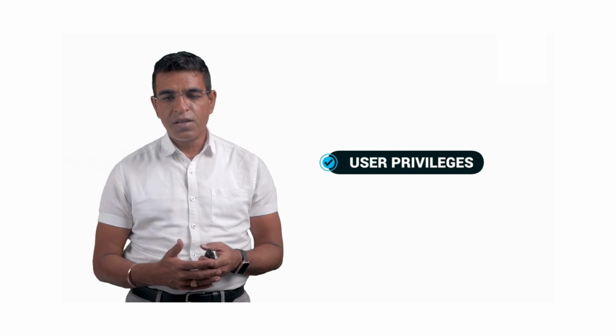Coming to passwords, many times we see common passwords being used. Where people share passwords, it is not possible to identify who creates or changes a record. So it has to be very clear that we should never use common passwords. Everybody should have their own individually identifiable password, known only to them. Coming to user privileges: the system configuration of the software does not adequately define or segregate user levels, and users have access to inappropriate software privileges such as modification of data. So we need to be very clear that user privileges need to be defined. What an administrator can do, what a manager can do, and what an analyst can do has to be very clearly defined whenever we are making a standard operating procedure.